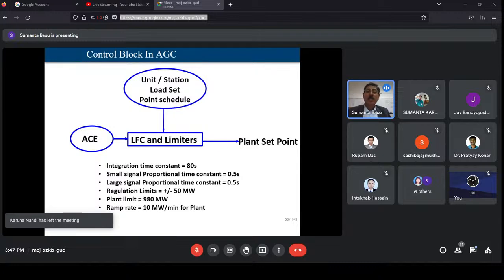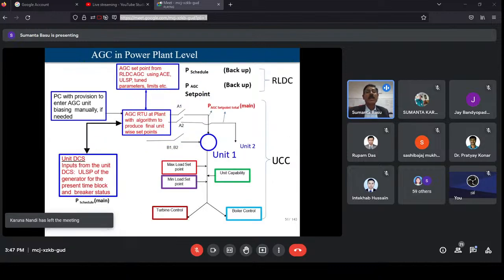The small signal proportional time constant is found to be 0.5 second. The large signal proportional time constant is also found to be 0.5 second. The regulation limit was plus minus 50 megawatt under AGC, and we are able to achieve that. And the ramp rate, whether ramp down or ramp up, is 10 megawatt per minute, and that also has been achieved. So this is one of the techniques of this AGC.